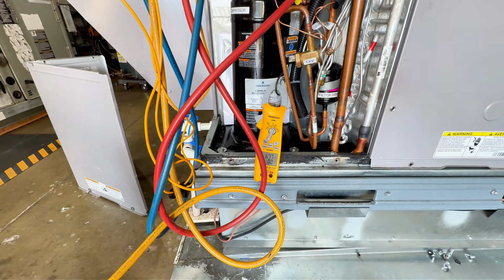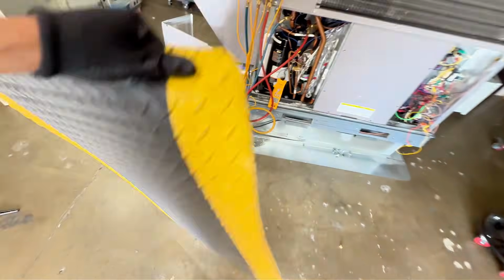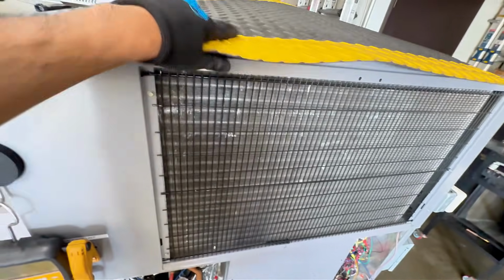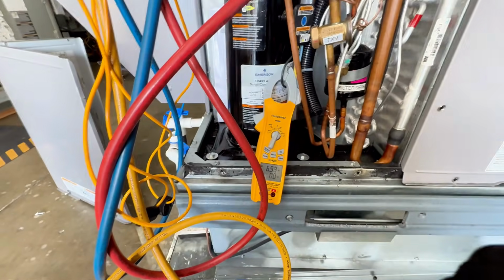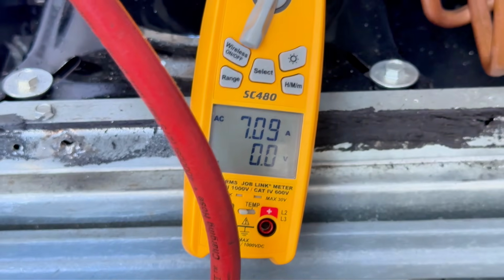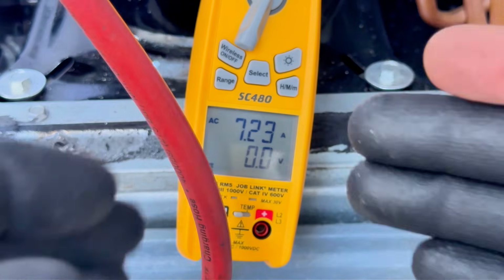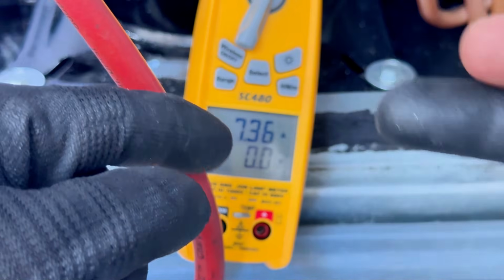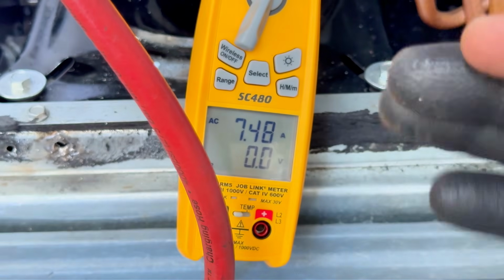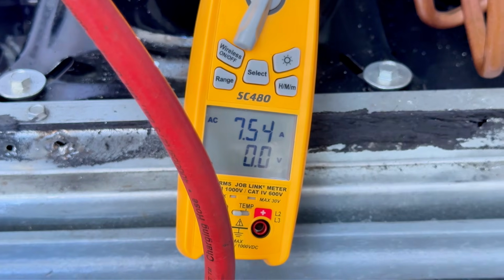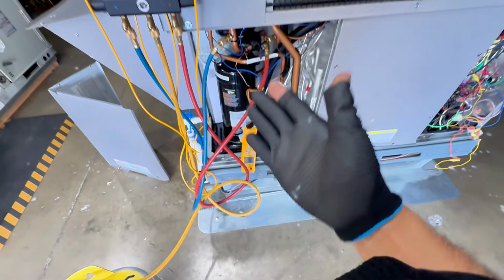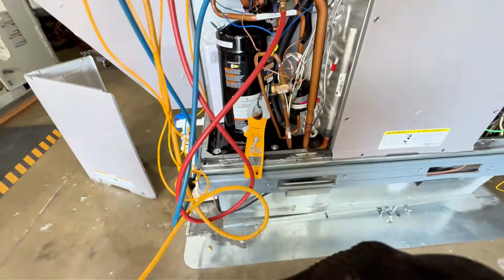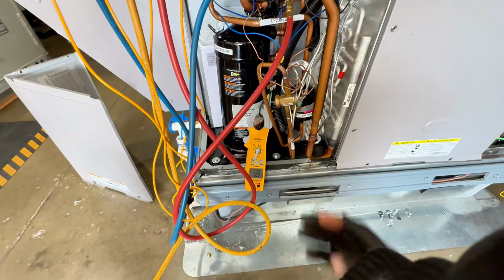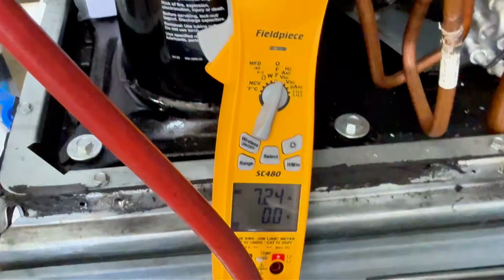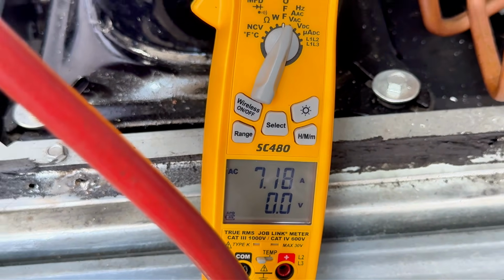So I'm going to go ahead and grab this mat, put it up here, and look at my amps go up. So that would cause the amps to go up. Just be mindful of that. We have to keep the condenser clean. If not, your compression ratio is a lot higher. Your compressor is working hard for no reason. Your amps go up. So that's one. And of course, superheat and subcool are important too. Right now, I'm just showing you two different ways where your amps would go up. So we'll let it go down to 6.8, 6.7, 6.8.